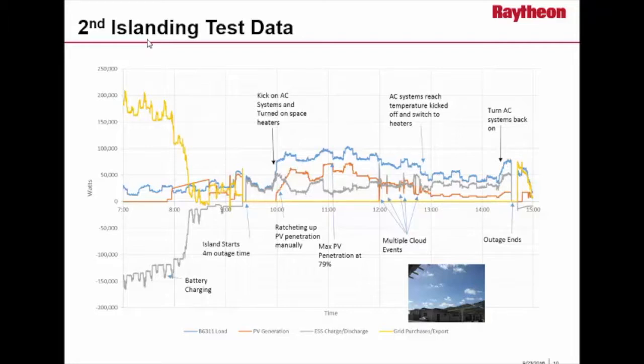Interesting things happened here in San Diego. The sky is usually perfectly clear, so the PV generation curve is normally the smoothest curve you can imagine. But on this day we had enough clouds to occlude the array, creating cloud edge events that completely took down the PV inverters and then brought them back online. That was an interesting use case for the battery, because it was able to hold up to those serious transients for basically a full load drop and recovery.